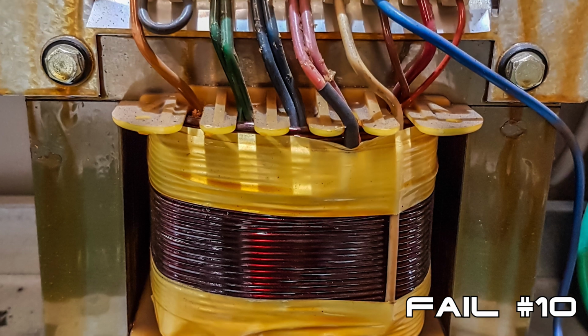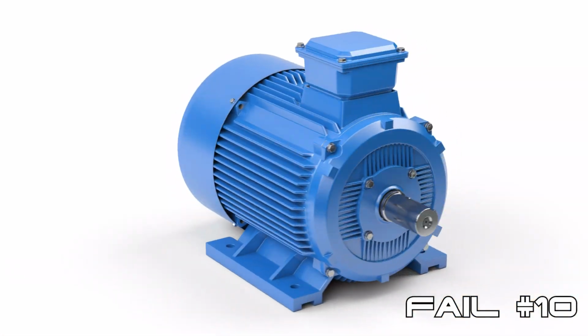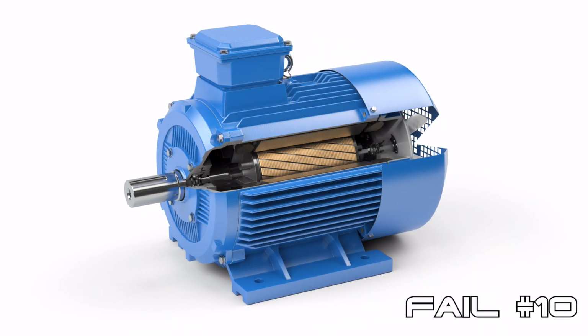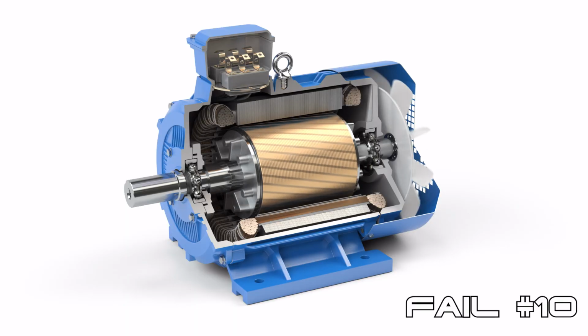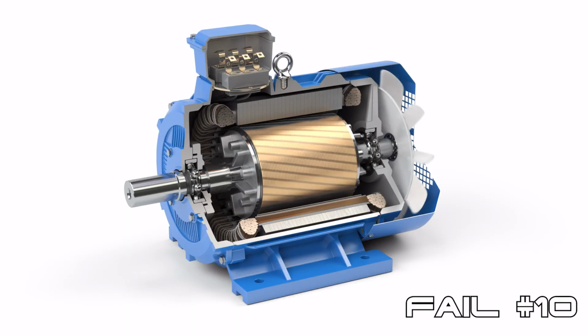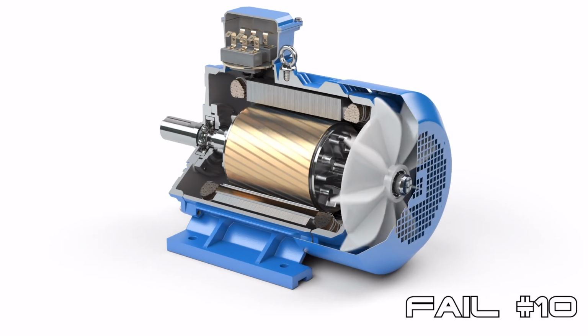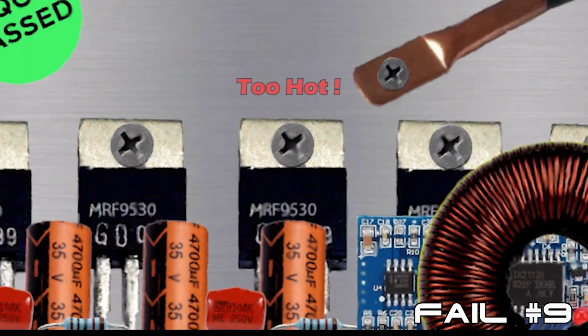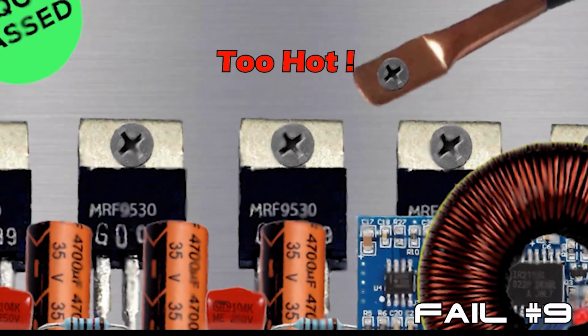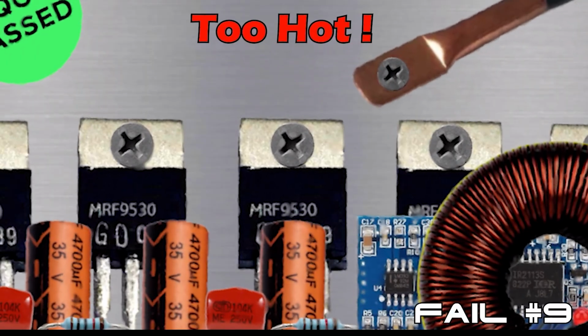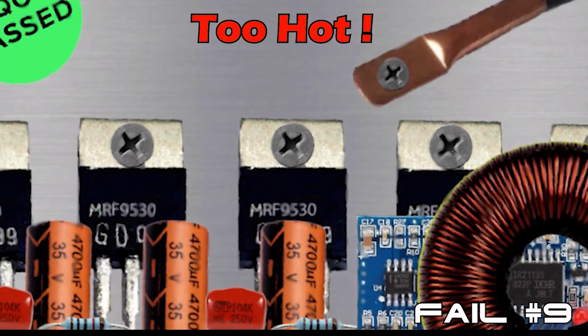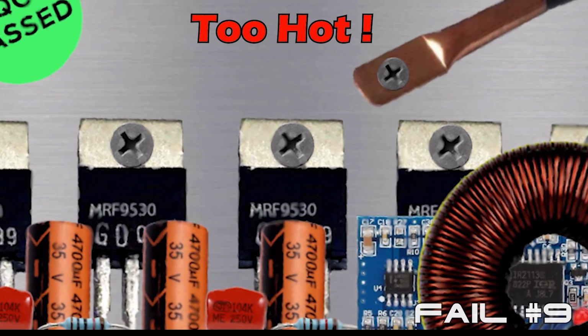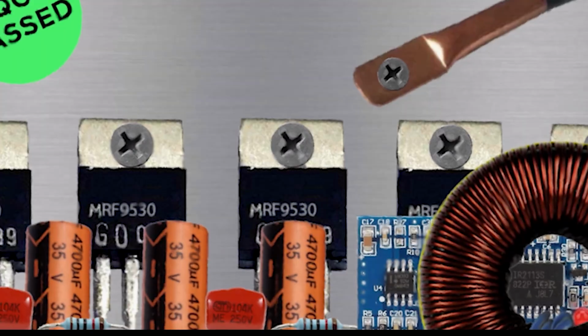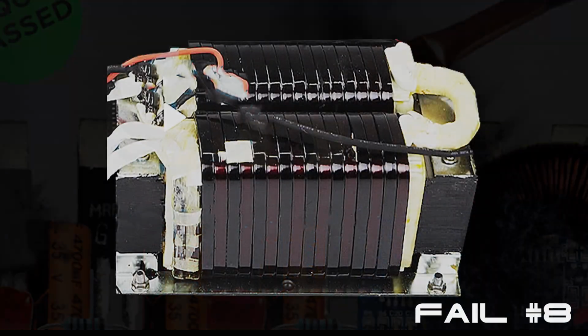Virtually any appliance that uses a transformer or electric motor. You may be able to start some of these high surge loads when your high-frequency inverter is new, but the long-term, repeated powering of these high inductance loads will shorten the life expectancy of your high-frequency inverter. Fail number 9. The components used in high-frequency transformerless inverters operate under higher levels of stress than the components used in low-frequency transformer-based inverters, due to their higher operating voltages and higher switching speeds, which can lead to excessive wear on the inverter's MOSFETs, diodes, and capacitors, again shortening the life expectancy of the inverter.